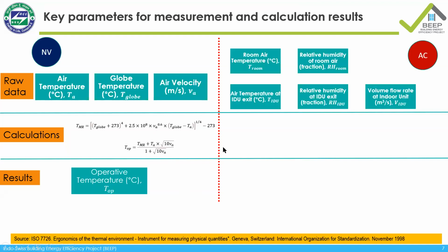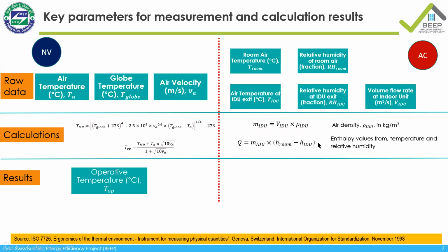The next thing was to do the monitoring in air conditioning mode. Here we had room air temperature and relative humidity, plus three parameters measured at the outlet of the indoor unit of the air conditioner: air temperature, relative humidity, and flow rate. Again, basic formulas were used to calculate enthalpy values from temperature and RH numbers, calculate mass flow, and then the heat load.